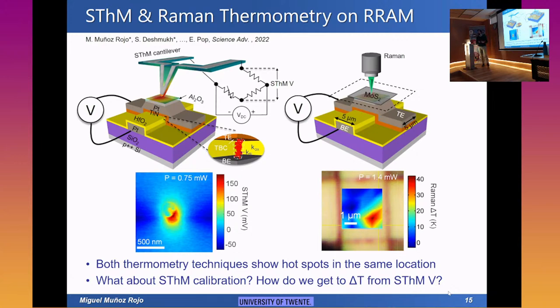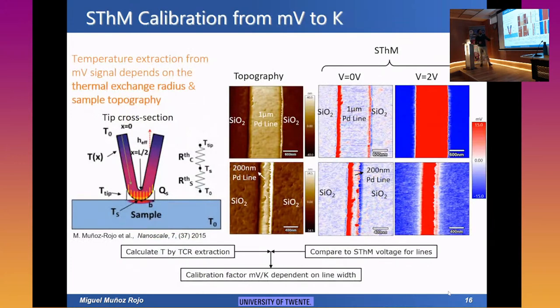So we need a different way to calibrate our SThM that can actually measure or quantify the temperature based on the signals we are getting. That's actually quite challenging. With SThM we have a very complex process of heat exchange between the probe and the sample surface, which depends, among other things, on the contact thermal resistance, the thermal exchange radius—the area over which heat is exchanged with the sample surface—and also other effects like topographic artifacts.